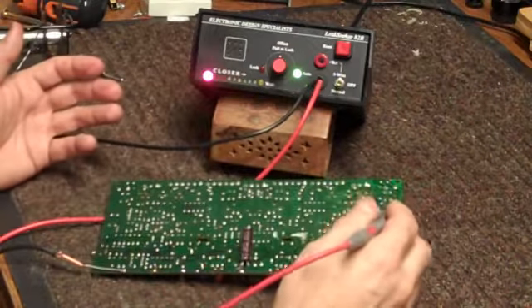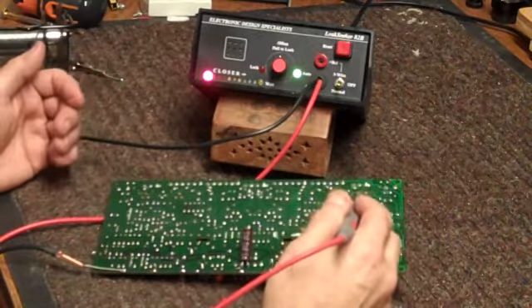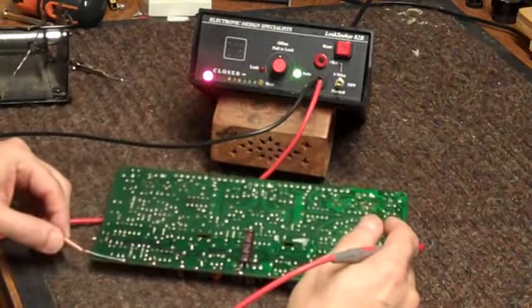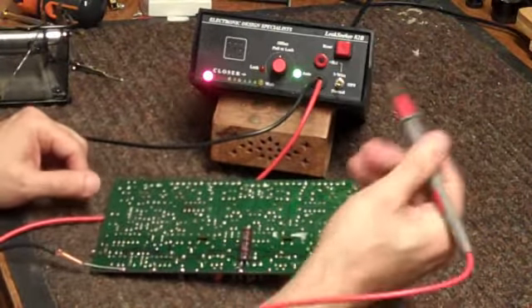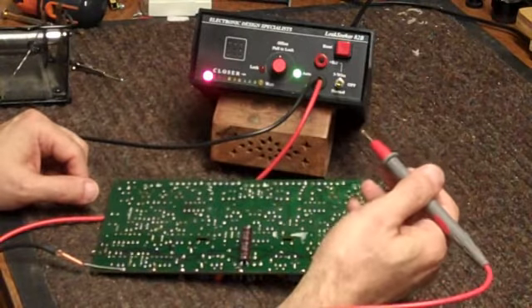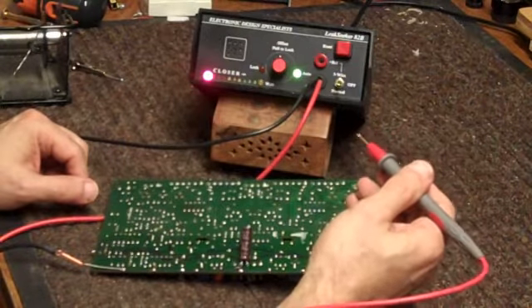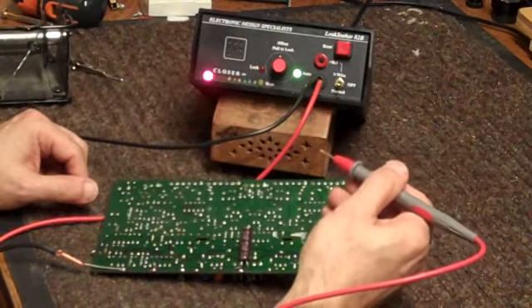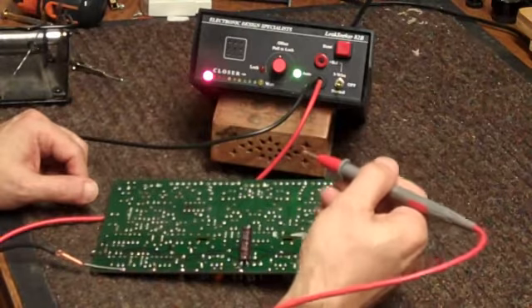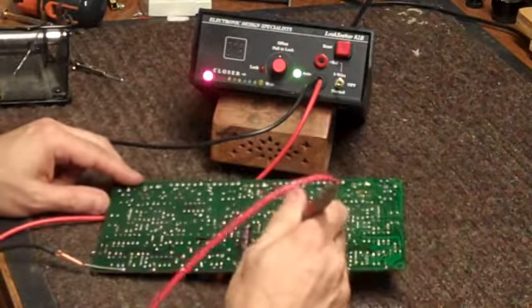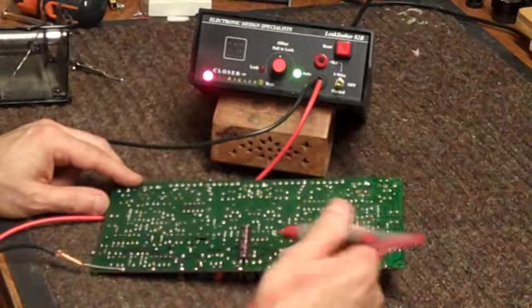So that's where the 3-wire test comes in. Right now, LeakSeeker in the 2-wire test is using black for ground as a reference, and on the red probe it's using a combination of two things: putting out a calibrated amount of current and voltage through the probe, and also measuring the change in current and voltage through the probe. That means every time we touch the probe here, it tries to charge up this capacitor.